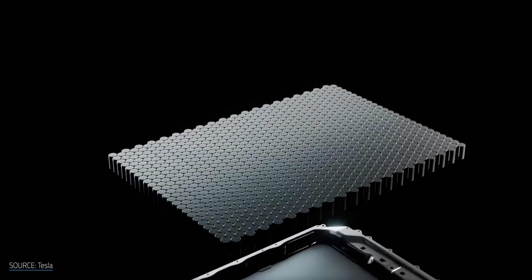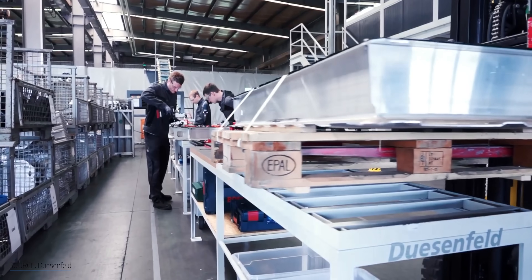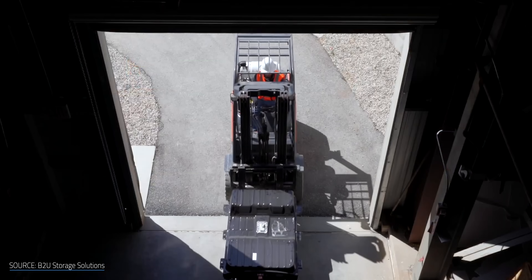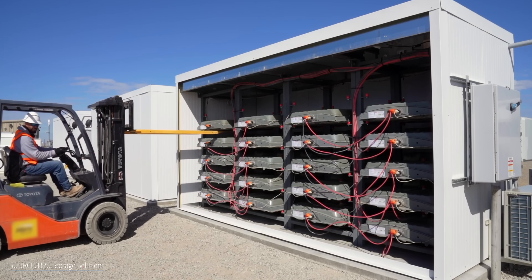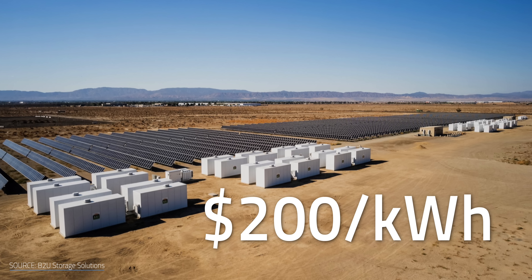This brings us to another innovation from B2U. Lithium car batteries are usually made up of thousands of roughly AA-sized batteries, literally glued together — close to 7,000 of them for a Tesla. Part of the reason it can be challenging to recycle or repurpose these batteries is because you normally have to break apart a pack to get to the individual cells. But that's not the case for the Sierra facility. Their cabinets are designed to accept packs as they are, instead of having to jailbreak each individual cell, which saves them time and money and allows replacement batteries to easily be tagged in when their time comes. Combined with their cabinet controllers and software designed to translate commands across different battery makes, it means they've made the process of reusing batteries in grid-scale storage much cheaper — an estimated 40% cheaper. Hall claims it costs less than $200 per kilowatt hour to install, which is well below the norm for lithium-ion battery storage plans.